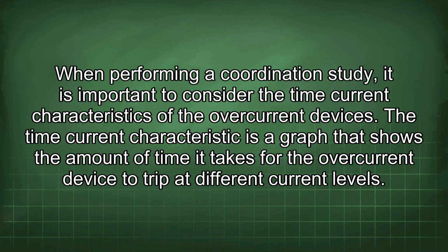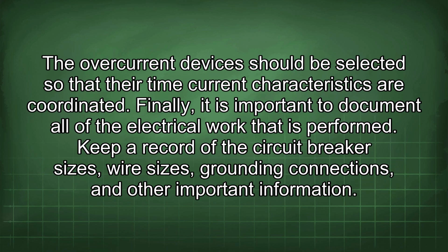When performing a coordination study, it is important to consider the time current characteristics of the overcurrent devices. The time current characteristic is a graph that shows the amount of time it takes for the overcurrent device to trip at different current levels. The overcurrent devices should be selected so that their time current characteristics are coordinated.